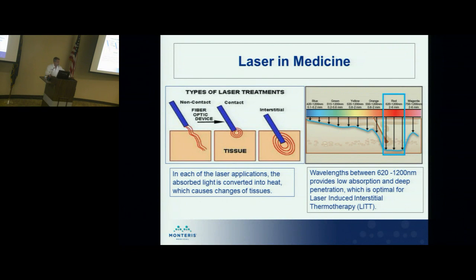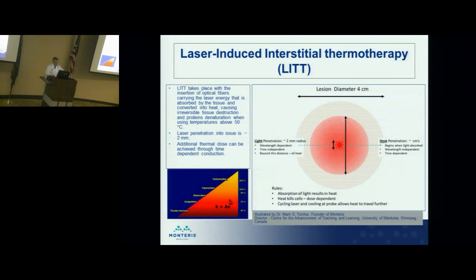And then there's interstitial laser, and that's what we're using here. This is the application you can see here. And we use a wavelength in this range. The red wavelength between 620 and 1200 nanometers provides low absorption and deep penetration, which is optimal for this type of treatment. What we do is we take an optical fiber that's carrying the laser energy at the tip of the probe that heats the tissue, basically heats the tissue up.